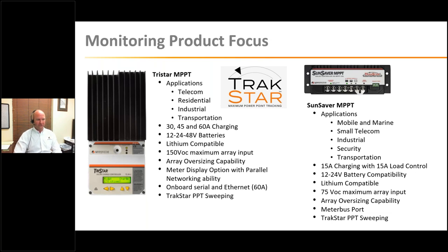A bit of a unique feature of these products is the ability to oversize the array, meaning you can put a substantially larger amount of power on the controller than it's rated for, and the controller will clip that and just run at full power with a straight 60 amp output continuously.